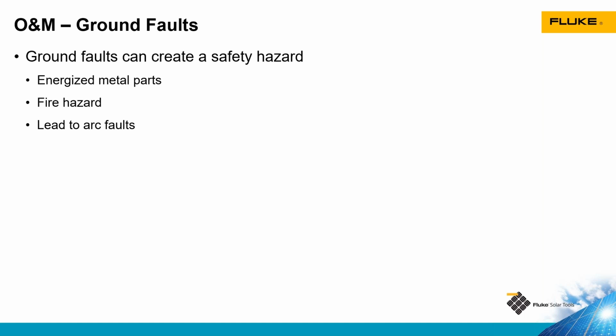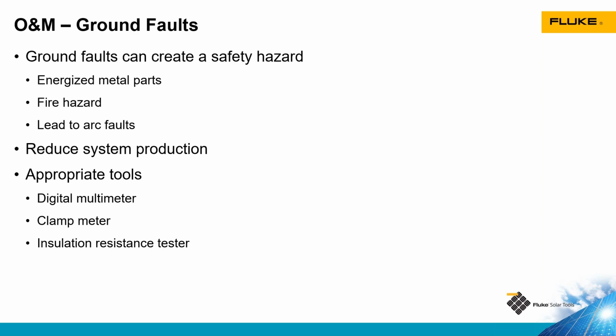Ground faults can be a safety hazard. We have current flowing to a non-current carrying metal part that may be energized, especially if we have a poor equipment grounding system. If there's no easy path for that current to ground and someone touches that metal part, they may become the path to ground, which causes a shock and possible electrocution. It's a fire hazard if there's arcing there, which would be an arc fault as well as a ground fault. That arcing may cause sparks that might lead to things like grass fires. It's also reducing system production. If I have current that's flowing to the ground, it's not flowing to my inverter where it should be going, where it's utilized by our loads. I can use any clamp meter, multimeter, or insulation resistance tester with the proper category and voltage rating for the system that I'm working on.